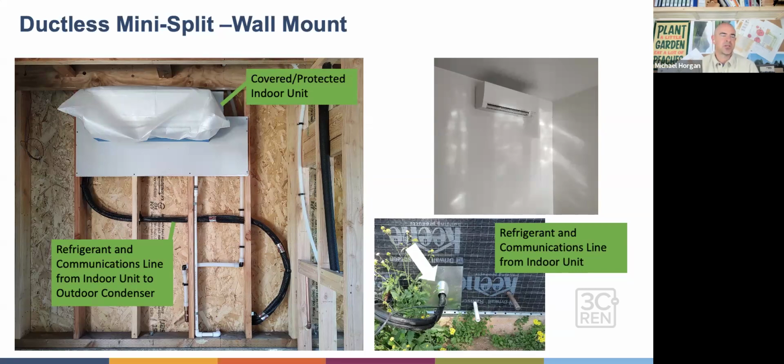You have to make sure your insulation company isn't putting rock wool. Say you've got a 2x6 wall. They're not just putting their 5.5 inch rock wool over that line because it won't compress enough for your drywall board to compress. And your drywall, though it will screw on in the moment, will eventually pop the screws as that dense insulation material starts to push back. So you have to make sure they cut around the line sets that are in the walls.